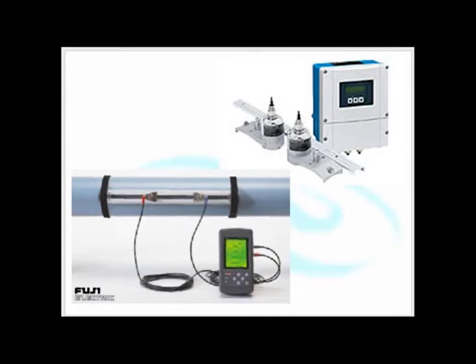Very, very thick plastic pipe will stop the sound. On the other hand, thin stainless steel metal pipe, it will go right through it beautifully. Thin plastic pipes, it will go right through beautifully. It will work lovely. It's on the outside of the pipe. It doesn't matter how nasty the stuff is on the inside of the pipe, the flow meter still reads. It's not especially accurate. With the best will in the world, you're going to be lucky if you're doing better than 2% accuracy with it. But it's on the outside of the pipe.